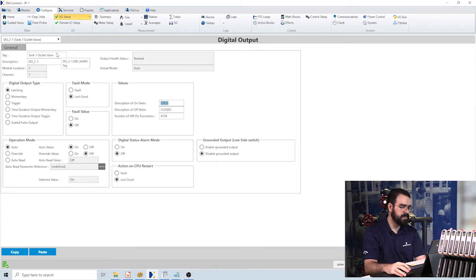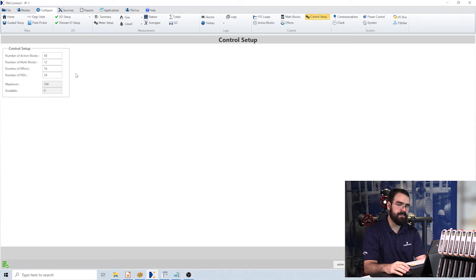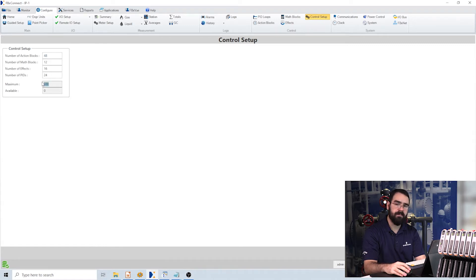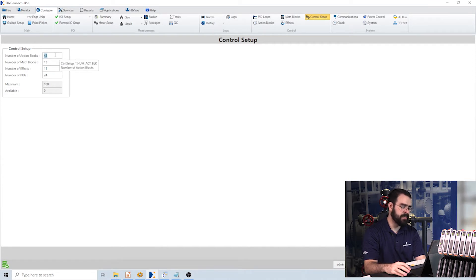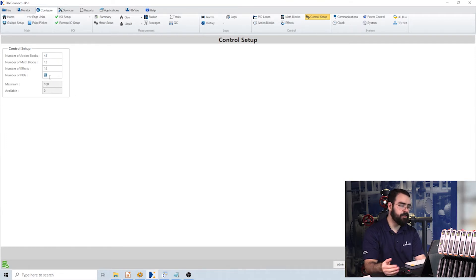Now let's go look at our control objects. In the FB3000, you have a dynamic amount of each of your standard control objects. You can see here on this control setup screen we have 100 maximum controls, which you can freely divide amongst action blocks, math blocks, effects, and PID loops. The standard setup is 48, 12, 16, and 24. But if you want 50 PID loops and 50 math blocks, or 75 action blocks and 25 effects, you can do that. It's all up to you according to your use case.